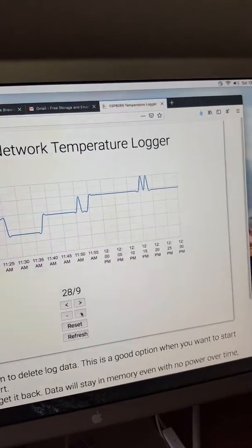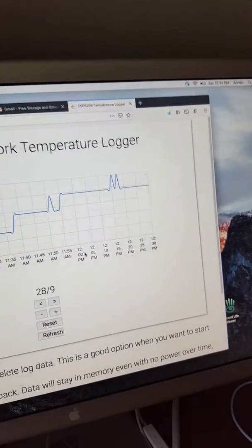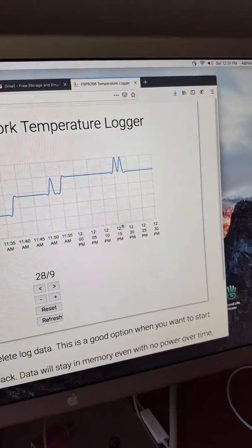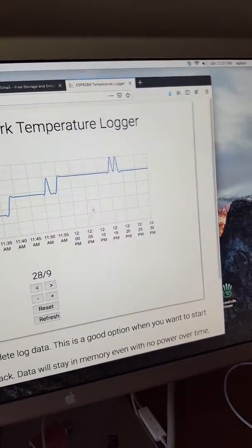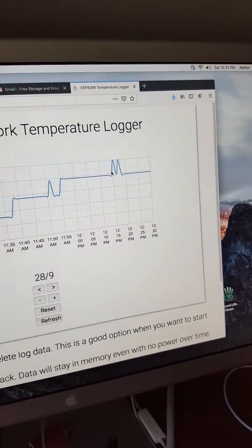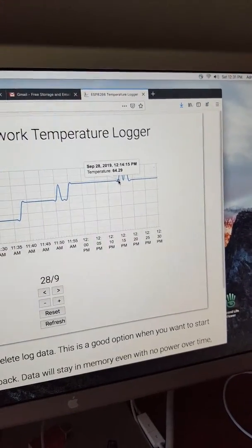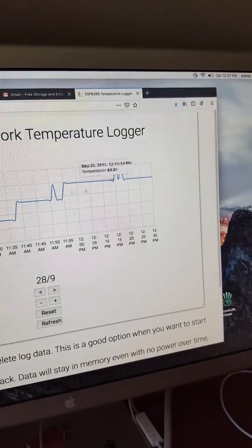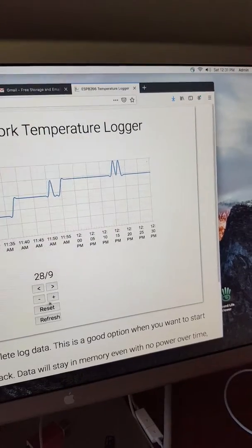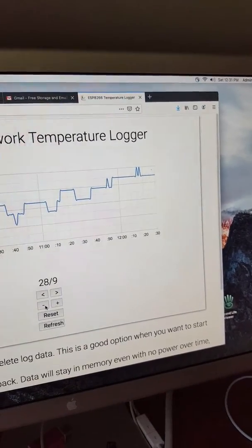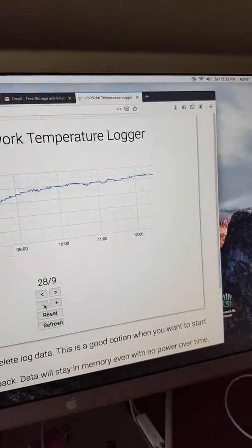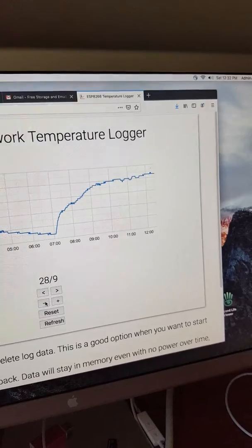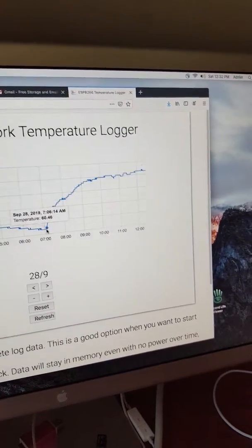So I just zoomed in. You can see the last... This is every 5 minutes. This is 5, so 15, 20, 25, 30. You can see the range of what's happening here. There's a little spike, second by second readout. You can see what's happening, and you can see if there are any issues with the sensor itself, any unusual spikes in the data reads that you shouldn't expect, especially if it's not happening in the environment.